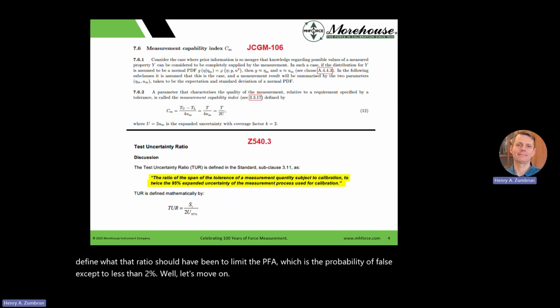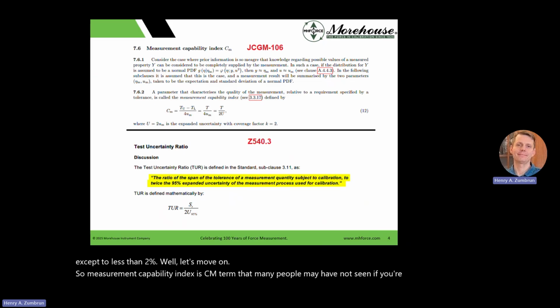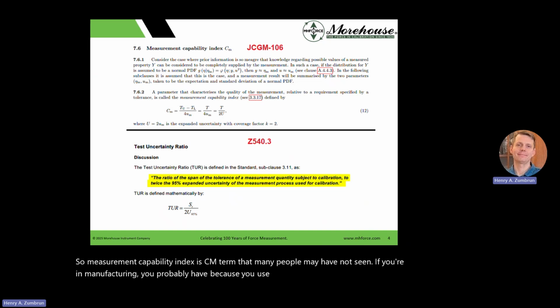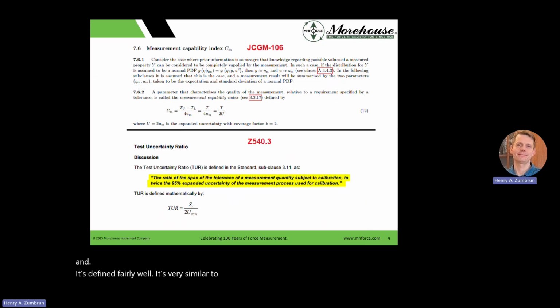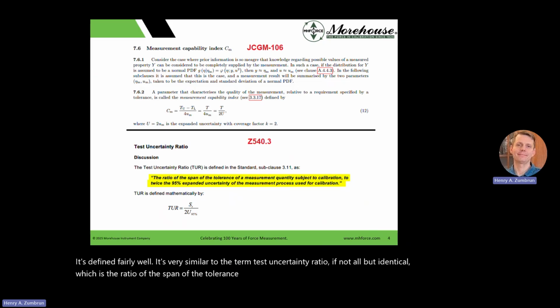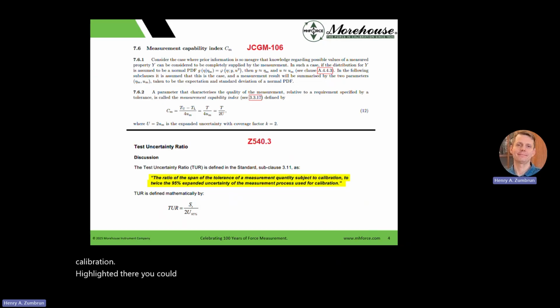So measurement capability index is a term that many people may not have seen. If you're in manufacturing, you probably have, because you use this term more so. This is in JCGM 106, and it's defined fairly well. It's very similar to the term test uncertainty ratio, if not identical, which is the ratio of the span of the tolerance of the measurement quantity subject to the calibration to twice the 95% expanded uncertainty of the measurement process used for calibration. Highlighted there, you could pause the slide and read it. They are virtually identical in every shape, way, and form.